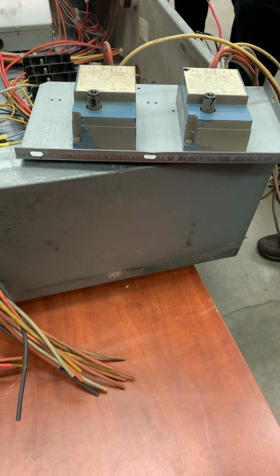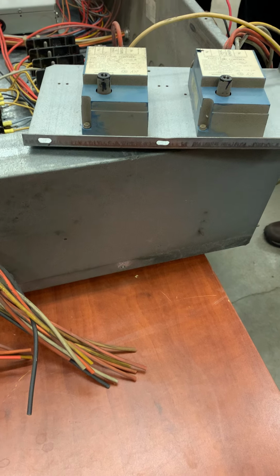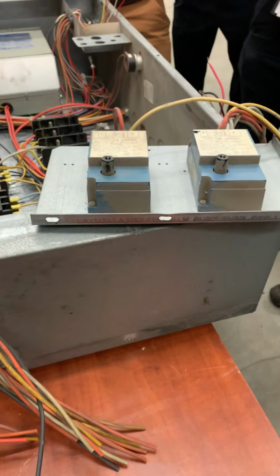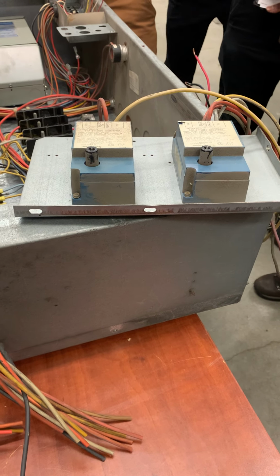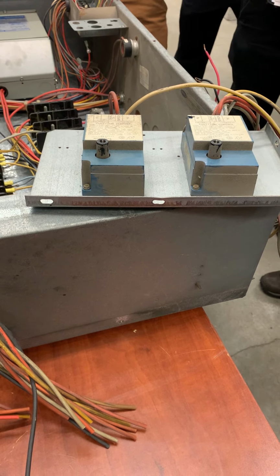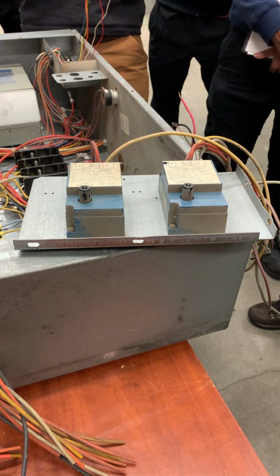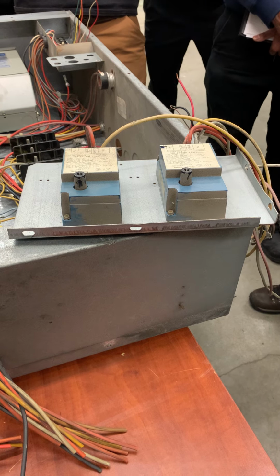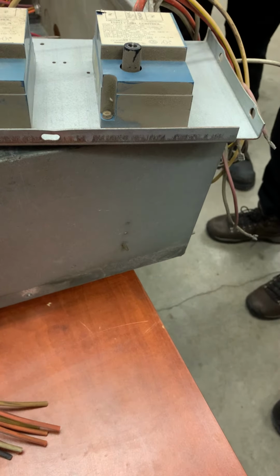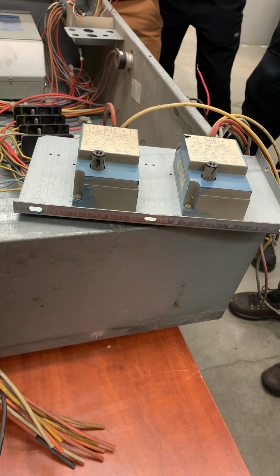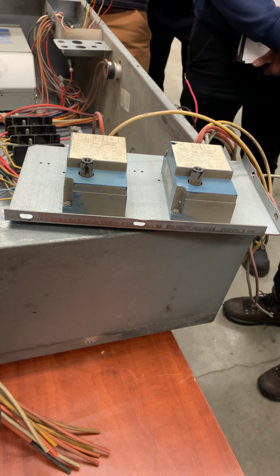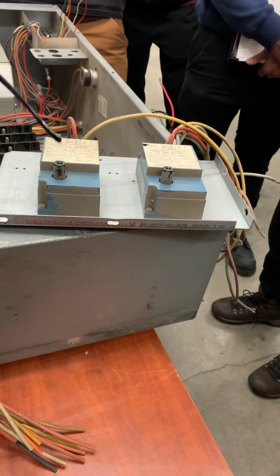Okay, and the reason I'm doing this is the following. Your ability to look at what's here and know what the system is important. You saw two ignition controllers, so you know you got two gas valves. Each ignition controller is controlling one gas valve. I could have a single ignition controller and a two-stage gas valve. Here I've got two individual gas valves. You looking at it, you pick that up, you say, hey, two ignition controllers, that means I got two gas valves. I've got two inducer motors. Next, those gas valves, what can you tell me about them? I'm looking for one or two specific words. And you'll get that information when you look at the ignition controller.